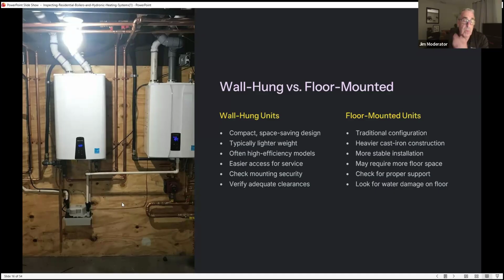I'm old enough to remember when these units didn't exist, unfortunately. And when they first came out, in my opinion, they had a bit of a bad rap that they weren't going to last long. But now I've been inspecting for many years, and I'm coming into older units from 2008, 2007, and they're lasting. So I tell people they should last as long with proper maintenance as a traditional boiler.